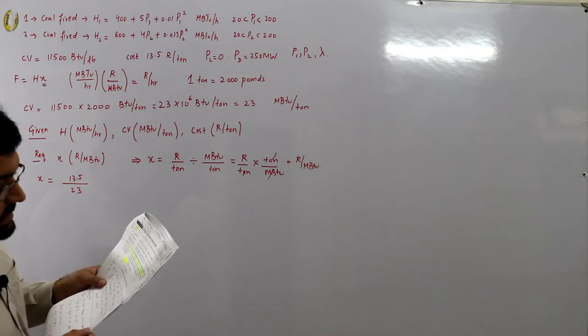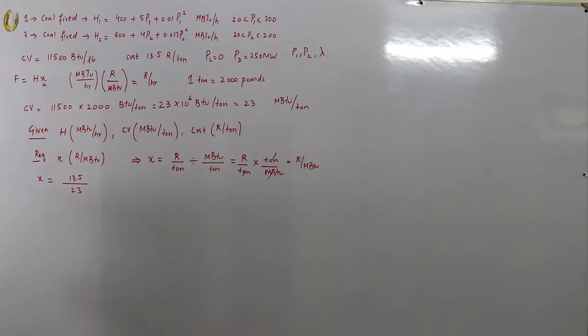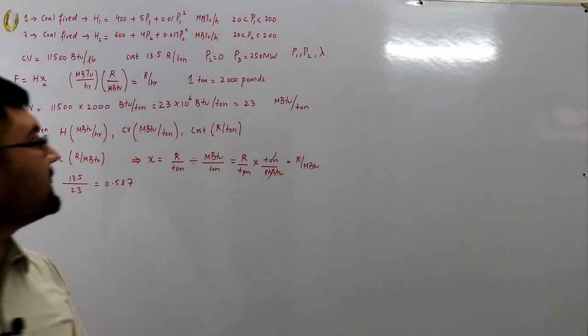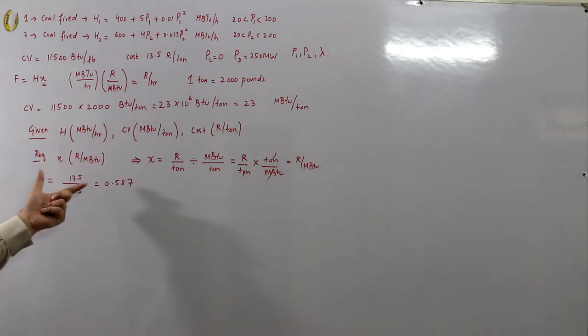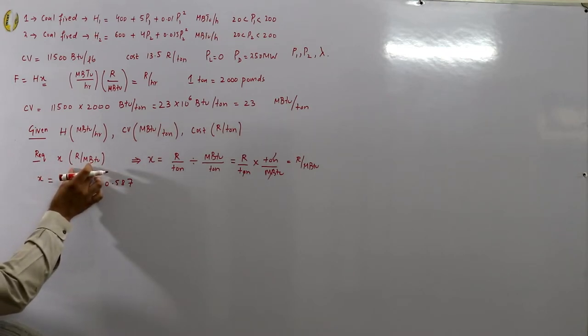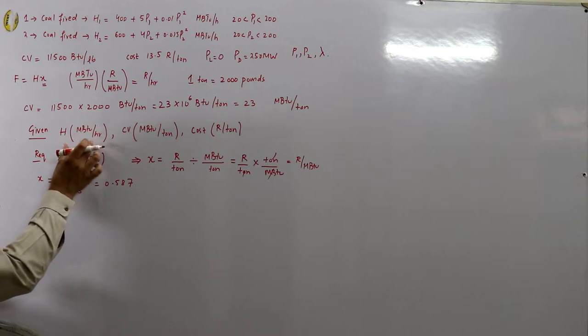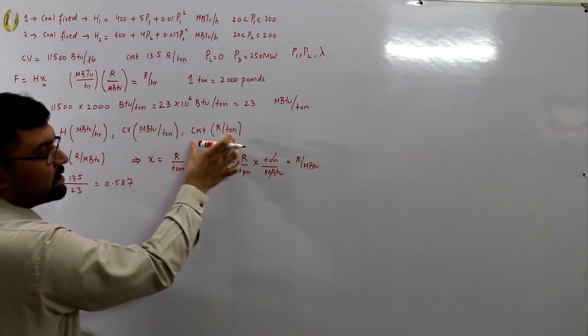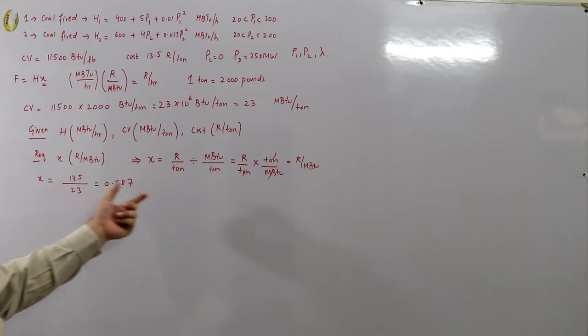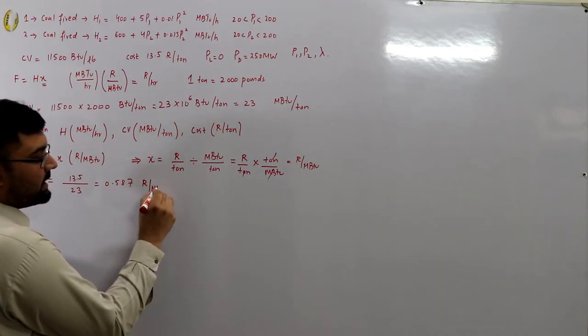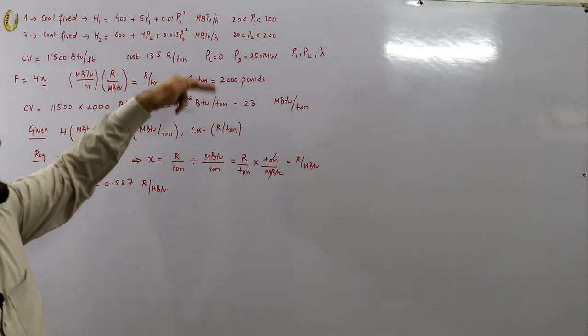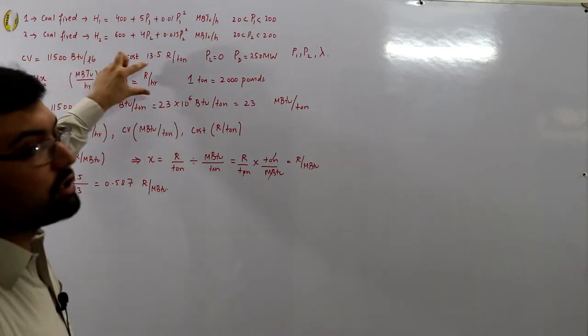This comes out to be x = 0.587. The key technicality here is working through the dimensions: x units are rupees per MBTU. Given h in MBTUs per hour, calorific value in MBTUs per ton, and cost in rupees per ton, we derive x = 0.587 rupees per MBTU, then multiply by h to get f in rupees per hour.